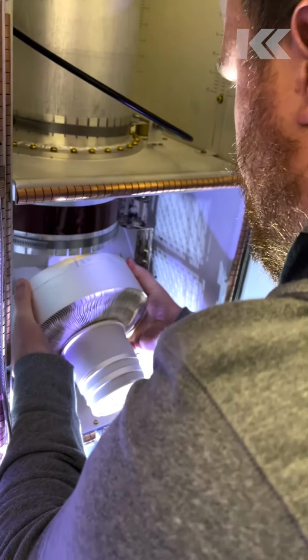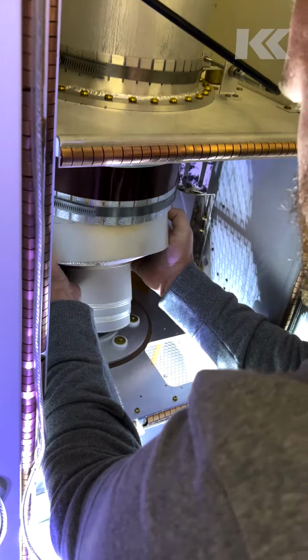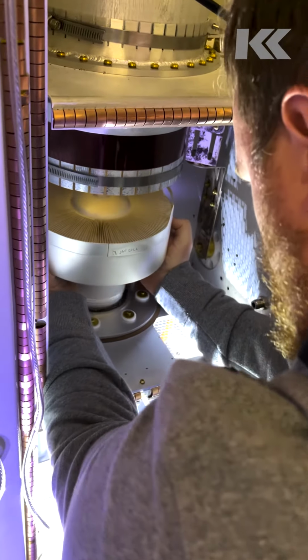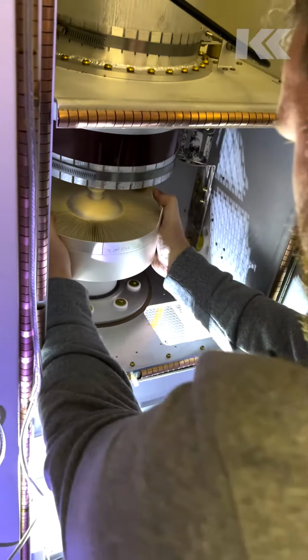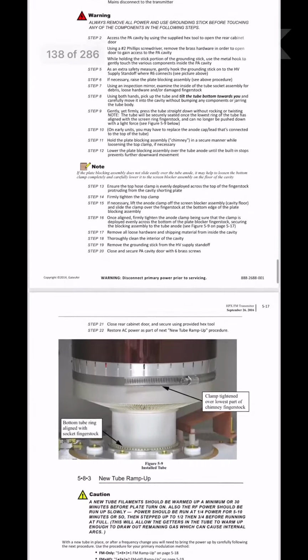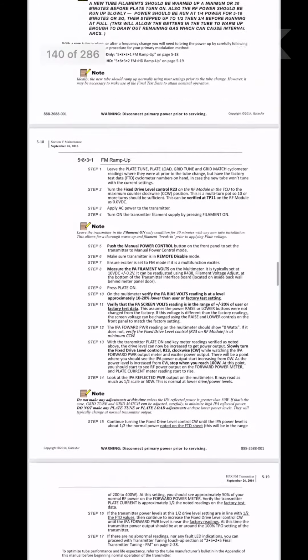This time, I measured 12 amps at the primary side of the filament transformer and we were good to go. It was almost like we got a do-over of the new tube ramp-up procedure, which I found helpful.